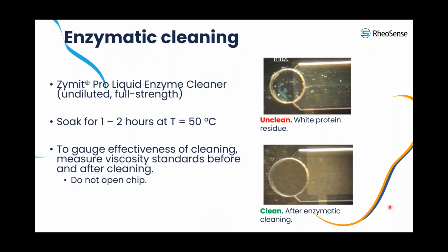Another essential cleaning process for protein samples is enzymatic cleaning, which is often necessary when there is a buildup of sample in the microfluidic channel. For enzymatic cleaning, we use Zymit Pro undiluted, which is introduced directly into the microfluidic channel.